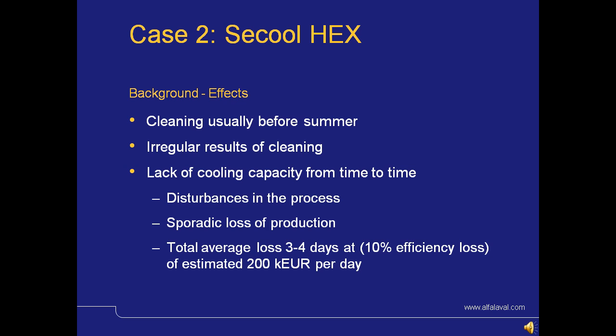The maintenance procedure used by the customer did provide an immediate improvement to the performance of the heat exchangers, but did not always last as long as it should have. The results of cleaning were irregular due to the fact that the customer did not know how well the heat exchanger was cleaned, since it wasn't opened, and this resulted into lack of cooling capacity from time to time. There were major disturbances in the process, as this is a vital part of the customer process, and sporadic loss of production. If the customer cannot cool the product enough, he has to reduce the production.